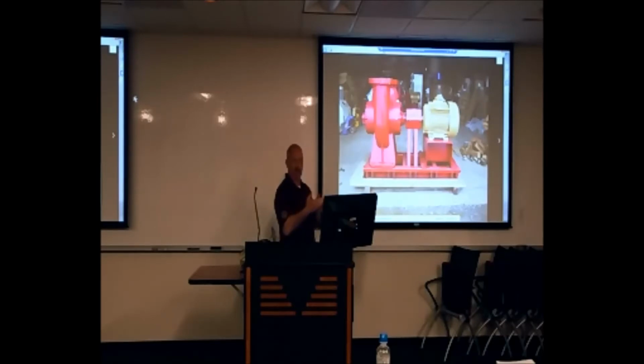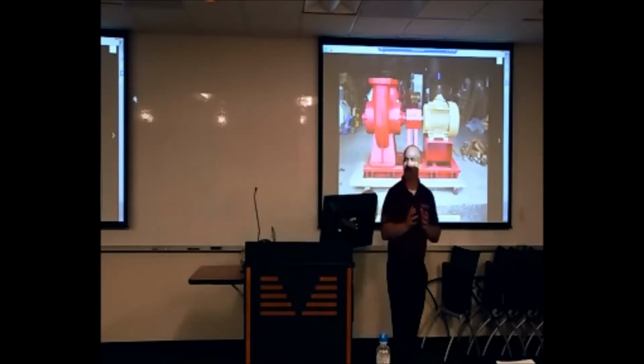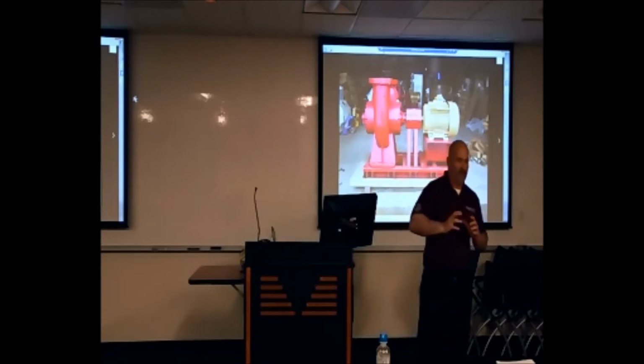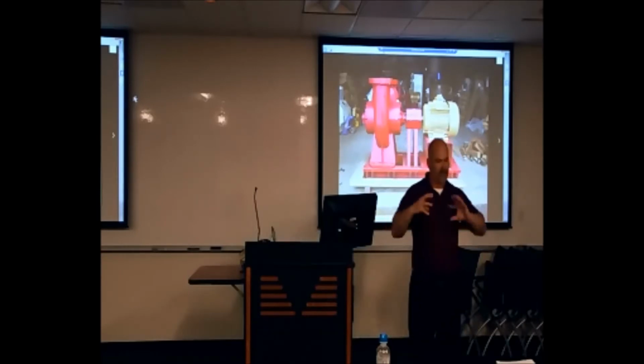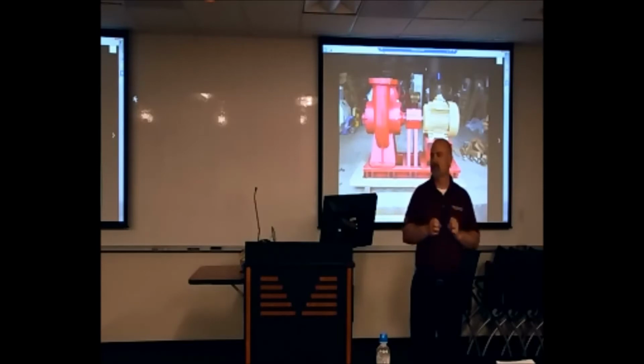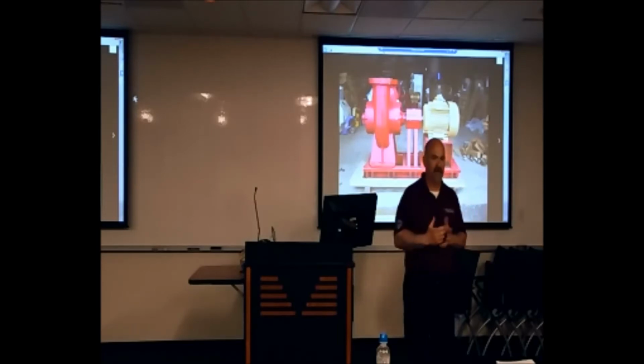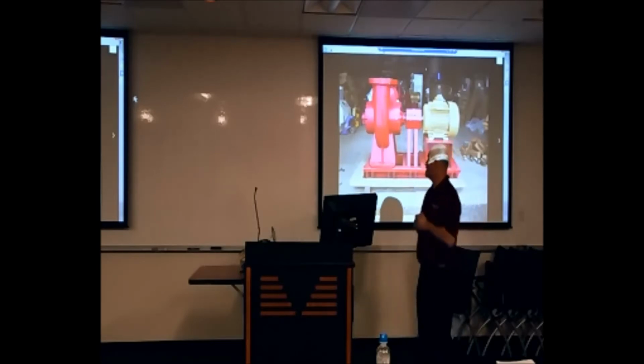You saw those arches in that thing. It actually allows for quite a bit of misalignment and will operate in that mode for a long period of time. I think the manufacturer gives almost an 1/8 inch misalignment on these things, so we don't need laser alignment and stuff like that. However, the more aligned it is, the less flexing it's going to do, the longer the coupler is going to last, obviously. So if you wanted the laser alignment, I have no problem with that. You can do that.